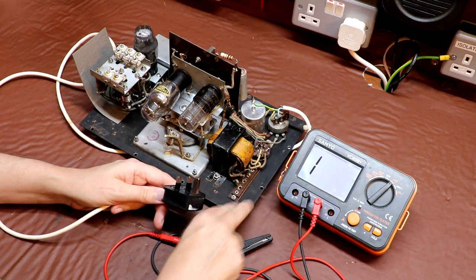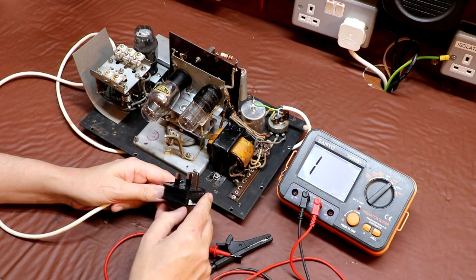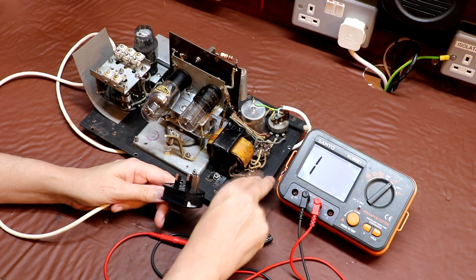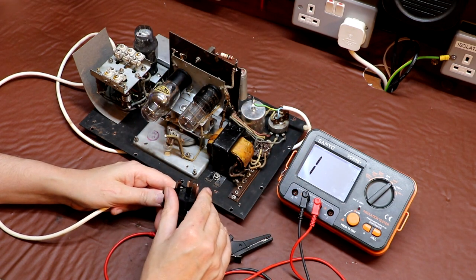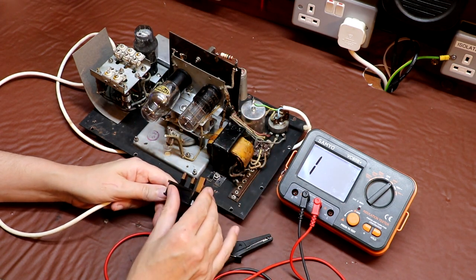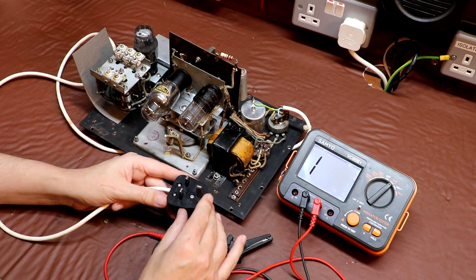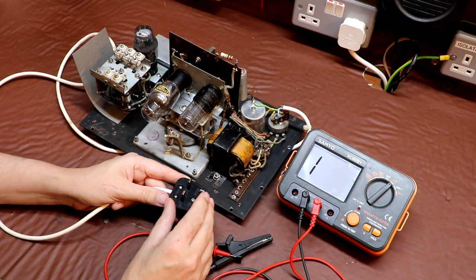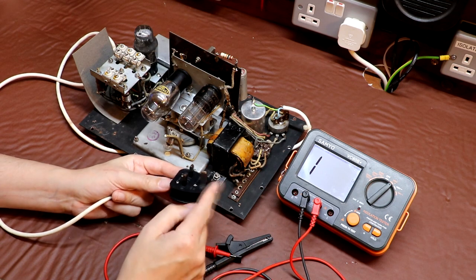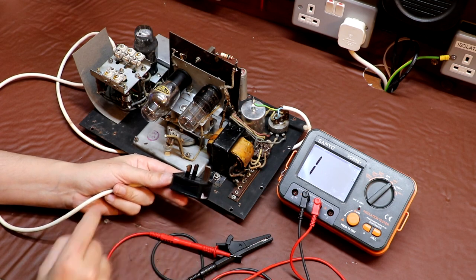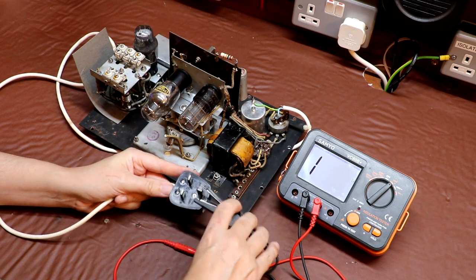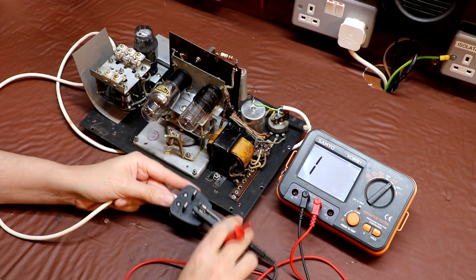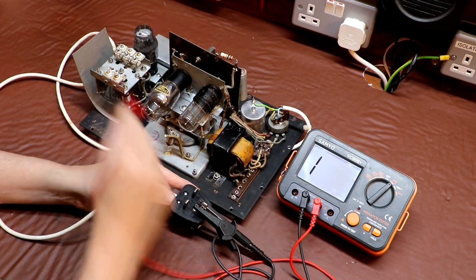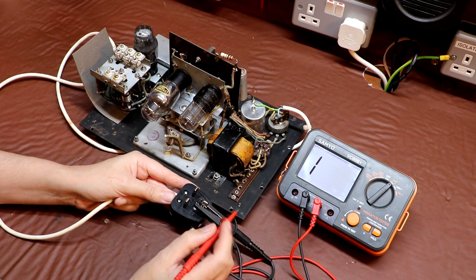Now, because this piece of equipment does have a metal chassis, if we get a fault on it, it's quite likely that all this metalwork could become live. If I was to touch it, I'm going to get a nasty electric shock. So really, we want to make sure that the chassis itself is earthed. Now, of course, the chassis is earthed through the mains plug here, through this pin on the end of our plug. So we're just going to do a continuity reading here between the earth pin and various parts of the chassis, just to make sure it's got a good earth on it.